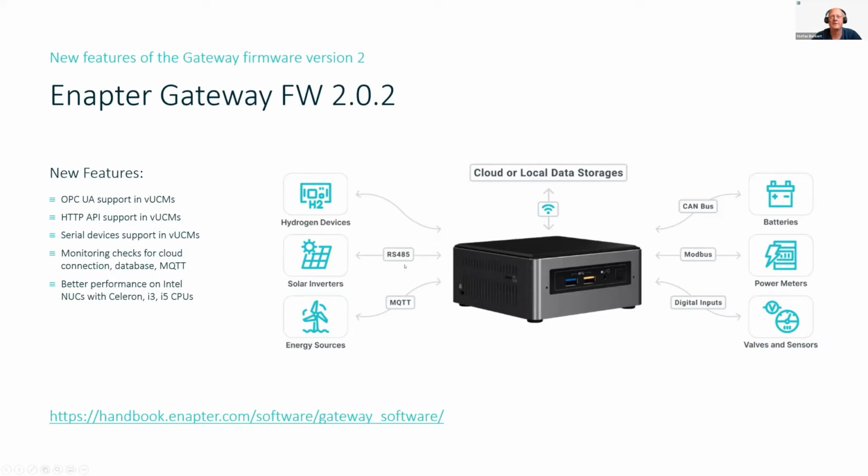As you can see left side on the screen, so we mentioned already the RS485 interface, and there was a question yesterday if we can directly collect data on that. We cannot, but we can get it. So the electrolyzer itself is just talking Modbus, and for sure parallelly to the cloud. But there are inverters or converters available on the market that translate the Modbus TCP communication into RS485. So if there's something needed that's available on the market, and if support is needed, we are here to help.